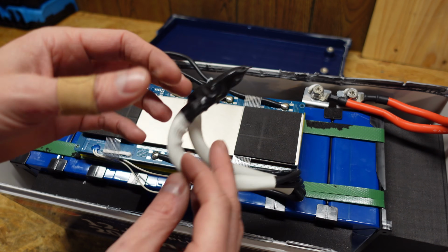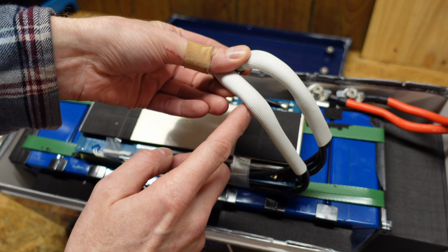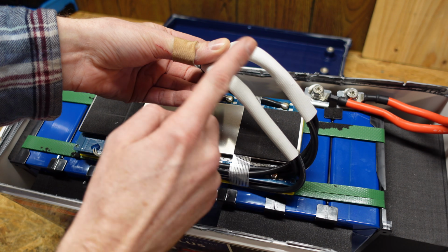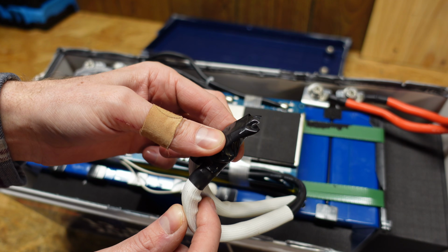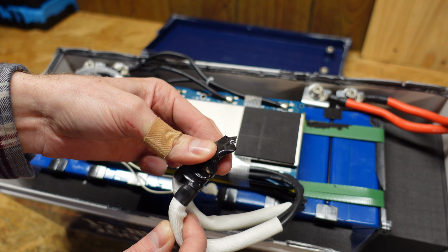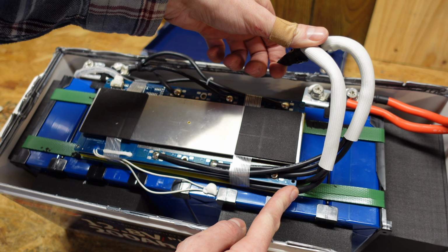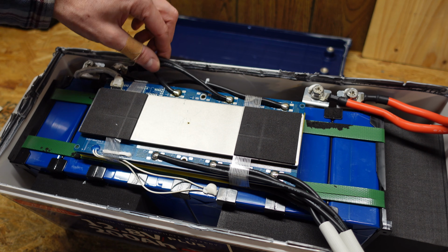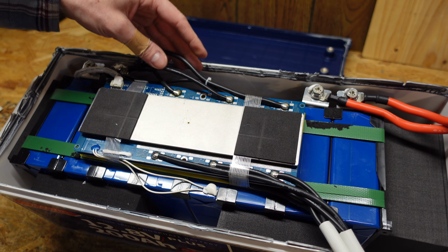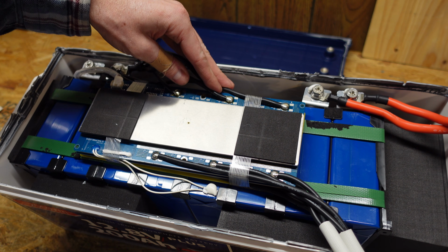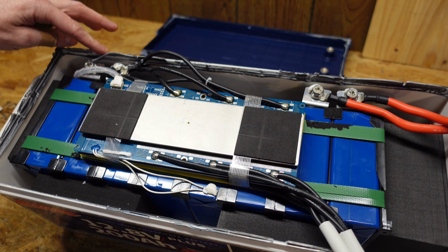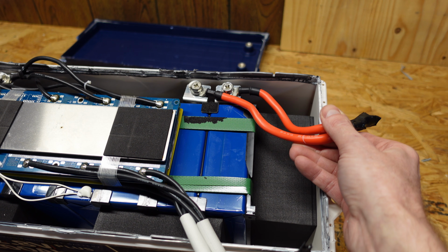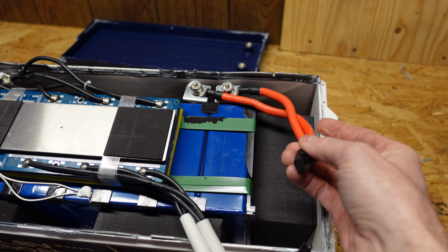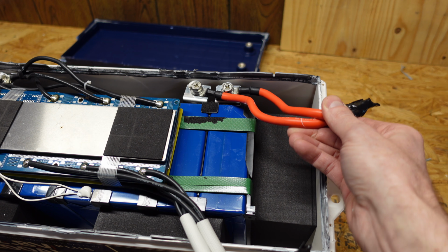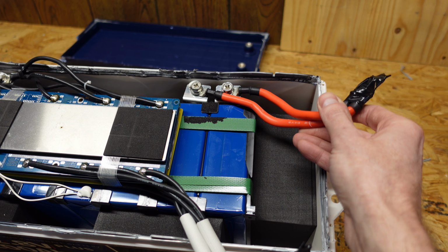Our cabling here, on the negative side, we have two separate runs of three conductors each, so there are a total of six conductors here, three conductors going to each crimped-on lug. The conductors are 10 gauge wire, silicone insulated, so a 200 degree Celsius insulation rating. The output wiring is the same way from the BMS, with a total of six number 10s going from the BMS to two lugs which tie into the battery. On the positive side, we have a pair of 6 gauge conductors, also silicone insulated wire, and this is some nice thick, beefy wiring here, so I'm very happy to see that.